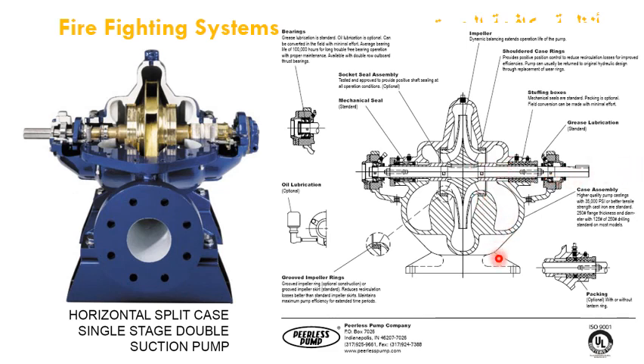Then the flow will be distributed equally on both eyes of the impeller from this side and this side, and according to the rotational motion of the shaft the impeller will rotate to collect and get the flow out from its outer diameter and to be collected in this volute casing, which increases from its smallest size until it reaches its maximum size at the discharge flange.